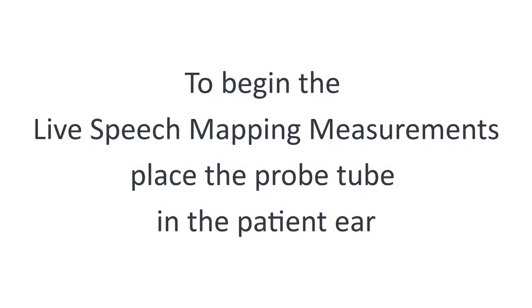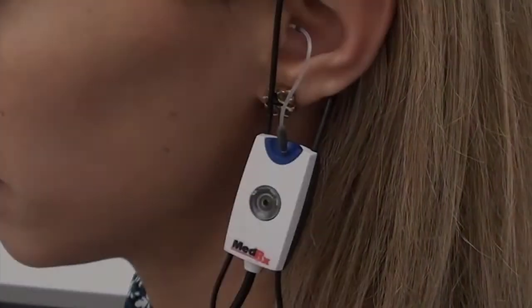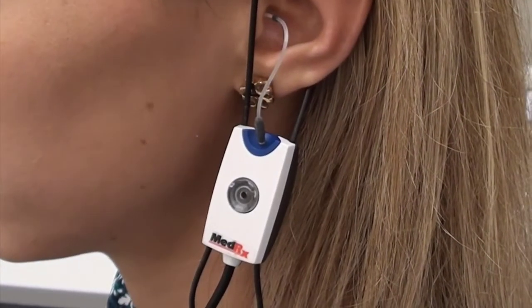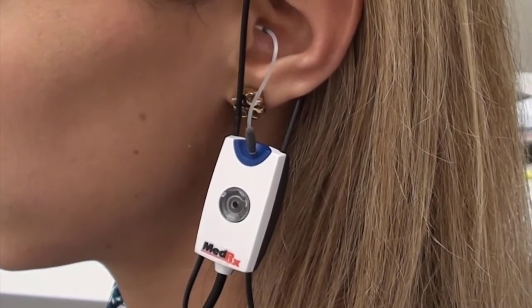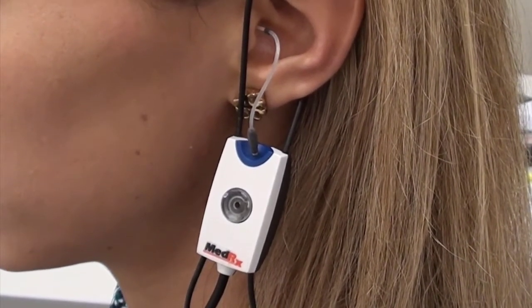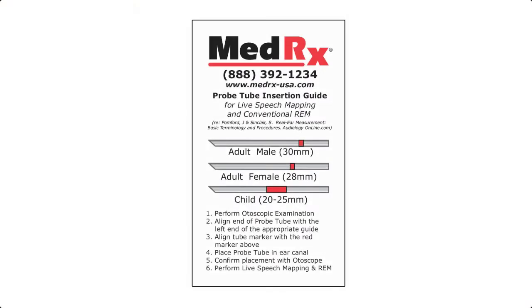To begin the live speech mapping measurements, you want to place the probe tube in the patient's ear. See the probe tube insertion guide that came with your kit.